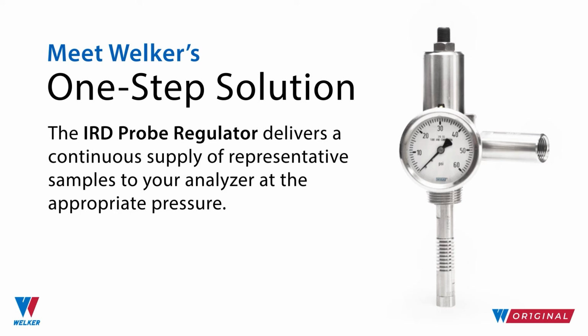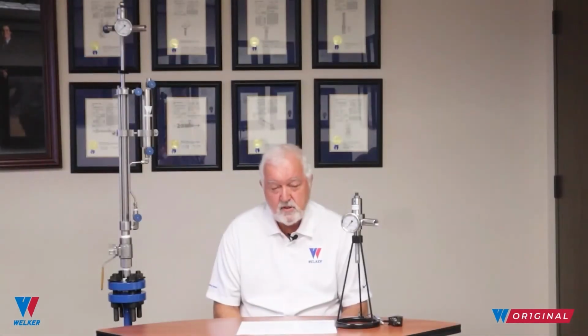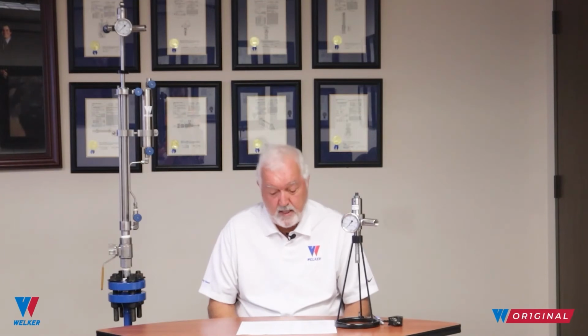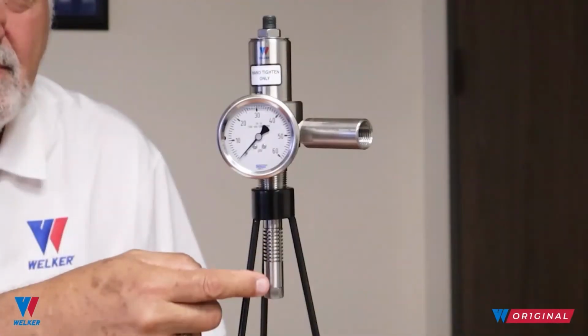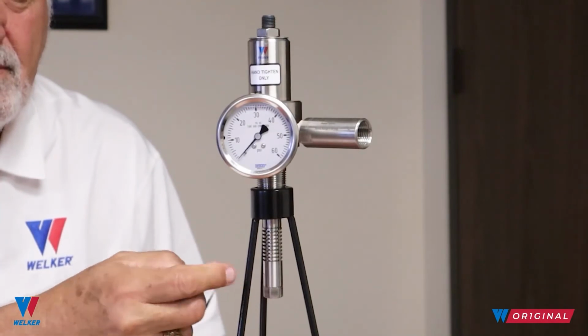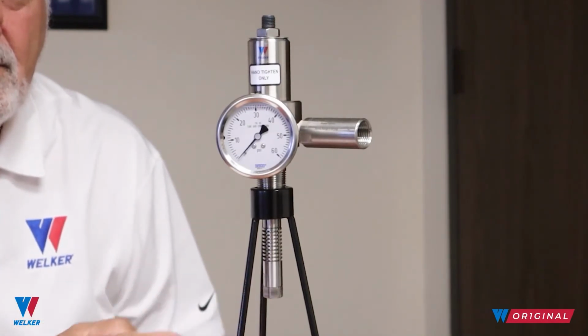After a series of tests at Chocolate Bayou, south of Houston, the innovative theory became reality. The probe regulator takes the pressure cut inside the flowing stream, letting the thermal fins at the bottom of the probe work to offset the Joule-Thomson effect that occurs after the pressure cut—one pressure cut and direct feed into the analyzer.